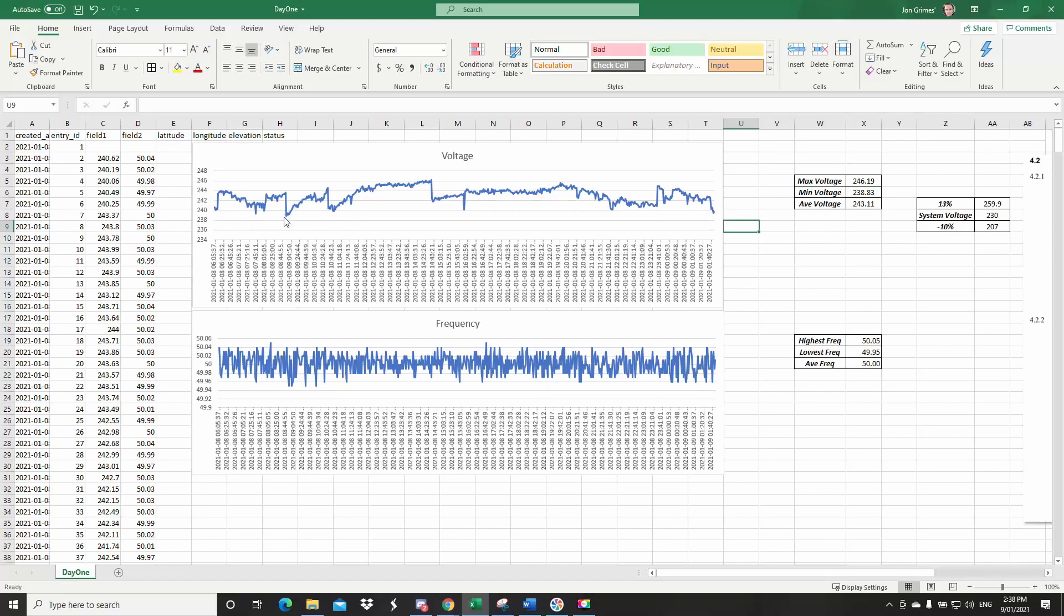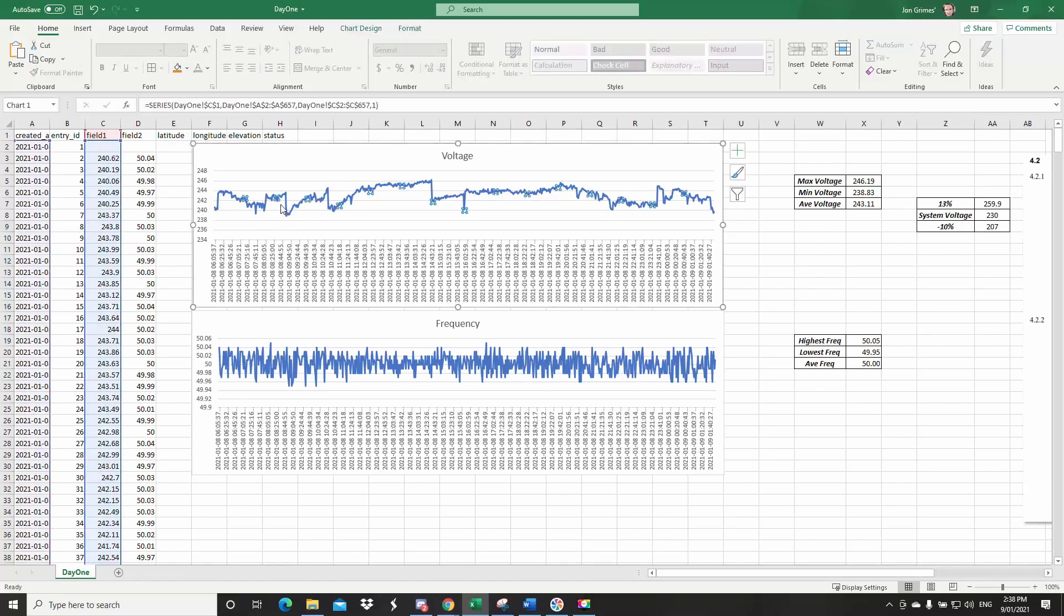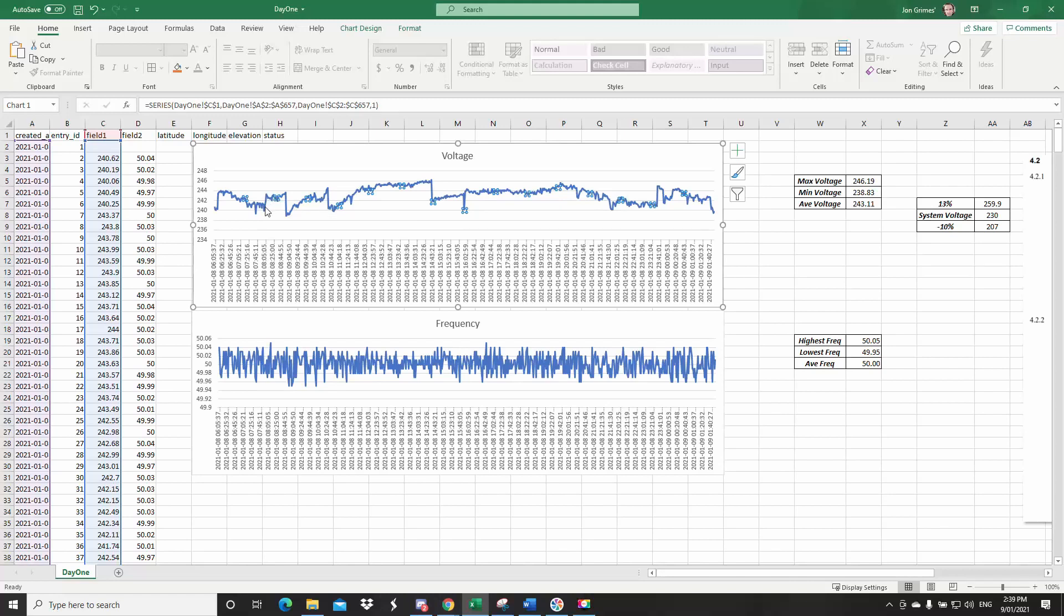Now in the voltage you can see these definite ups and downs, these big sharp straight lines. Now that would be due to voltage control in the network. So at the substations the big power transformers have tap changers and they'll have a predefined voltage that once it hits it'll go up and down. And that's what you'll see is happening here.